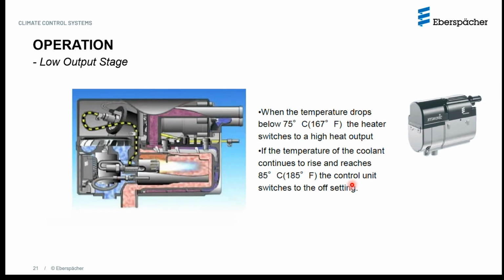It'll basically be a small incremental change with every degree rise of temperature. So over here, once the heater switches to a lower output, when it drops below the minimum, that's 167, the heater switches back to a high heat output. Because the first generation heater had only two heating outputs, it was very simple, whereas in the case of the third generation, as you know, there are multiple steps. So it also has a minimum range. If it drops below the minimum temperature of the coolant, the heater will also switch back to the higher outputs. So it can work both ways. It can go from a higher level to a lower level, or from a lower level to a higher level for the output of the heater.